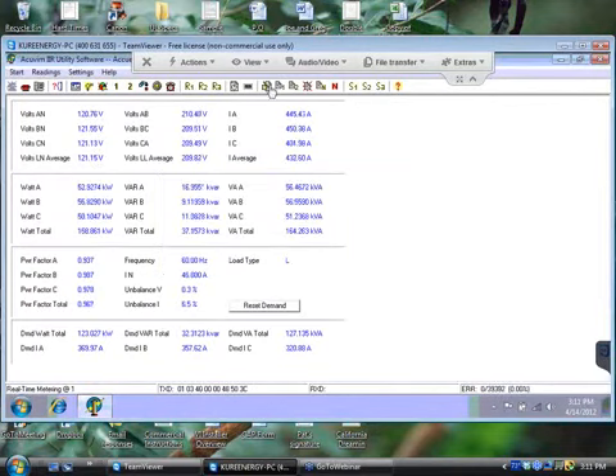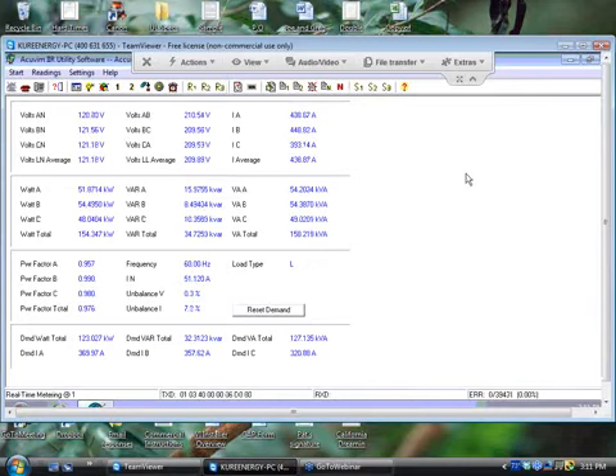Let's get these signs out of the way. I want to hit the view on this one and scale it up so you can see it better. And here we go. Look at how active this system is, over 400 amps of current going through, but look at the power factor at 0.97, 98. Big difference. kW drawing 160 kW instantly.